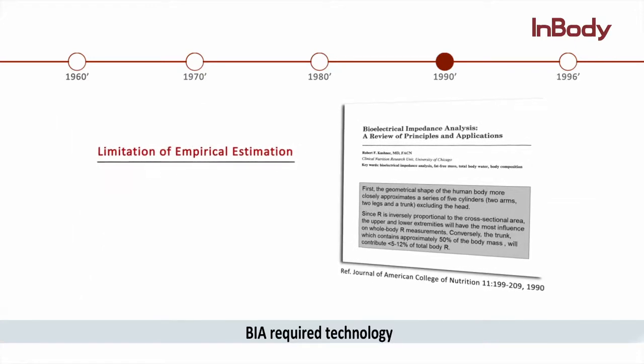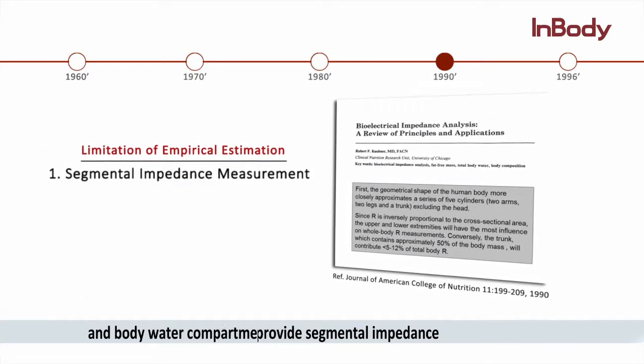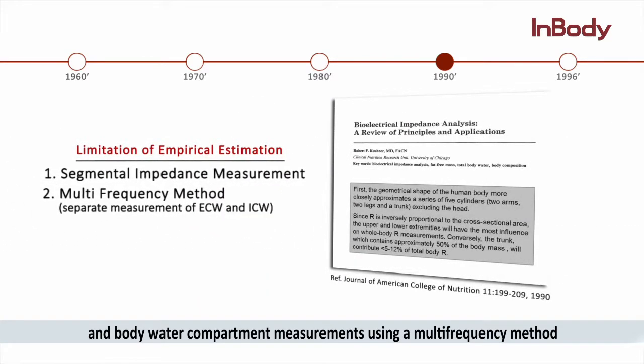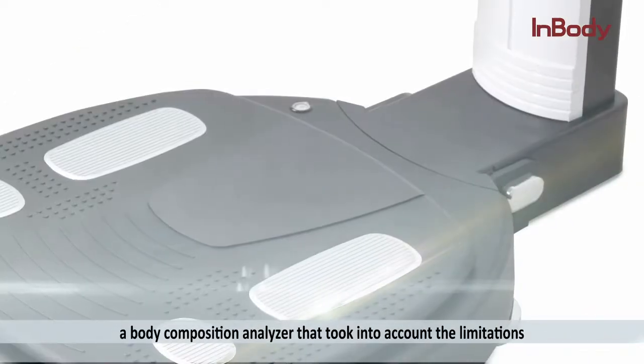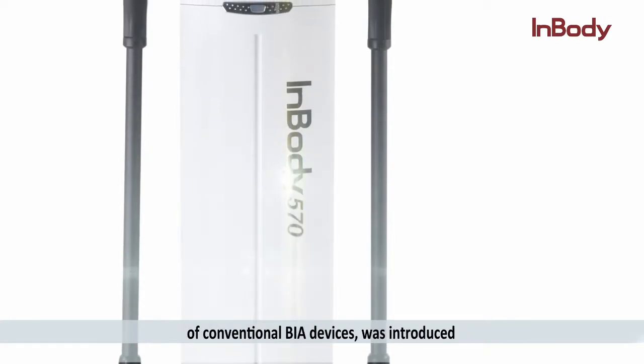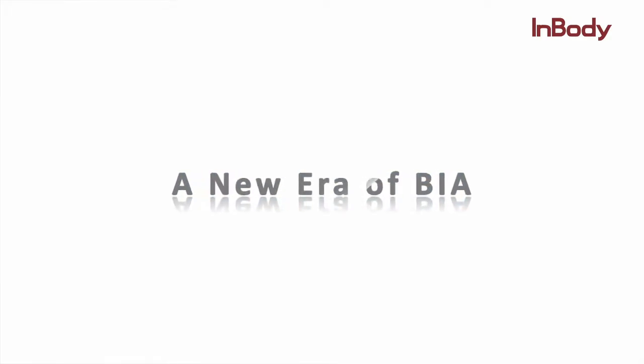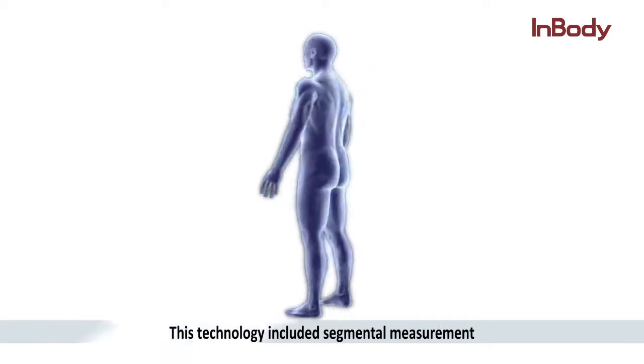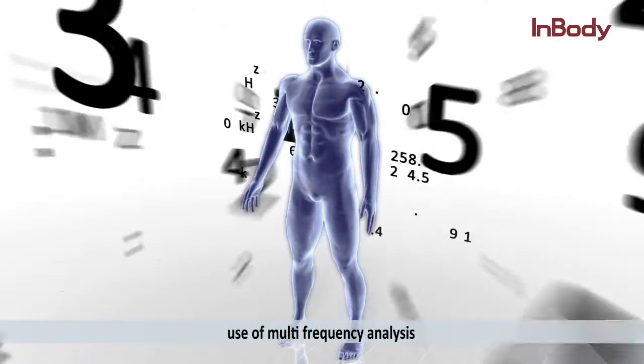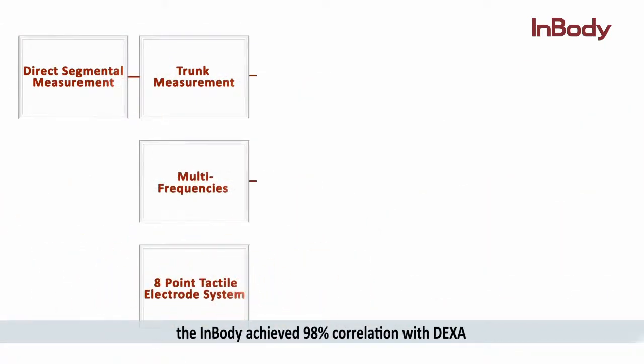BIA required technology that could provide segmental impedance and body water compartment measurements using a multi-frequency method. Then in 1996, the InBody — a body composition analyzer that took into account the limitations of conventional BIA devices — was introduced. This technology included segmental measurement, multi-frequency analysis, and an eight-point electrode system. With these advancements, and without the use of empirical estimations, the InBody achieved 98% correlation with DEXA and an impressive reproducibility of 99%.